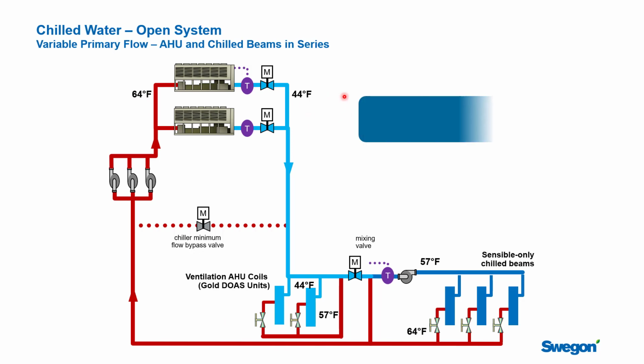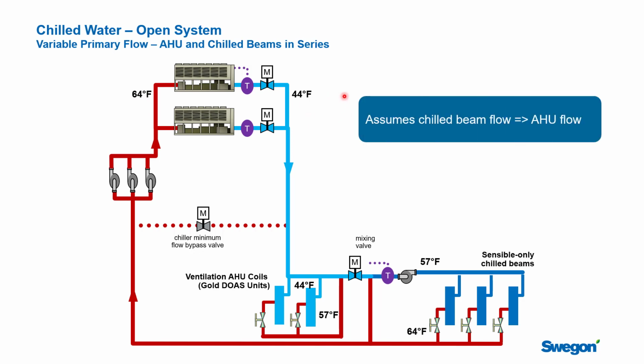Well, this is only going to work if your chill beam flow exceeds your air handling flow. And it is so important to slow down, stop, and look at your flow rates that we're going to walk through an example together so you appreciate it. Now, we think this is a good idea, that it should definitely be considered in your chilled plant design for chilled beams, but we want you to appreciate the care that has to go into this and the understanding particularly about how your system will behave at part load conditions.